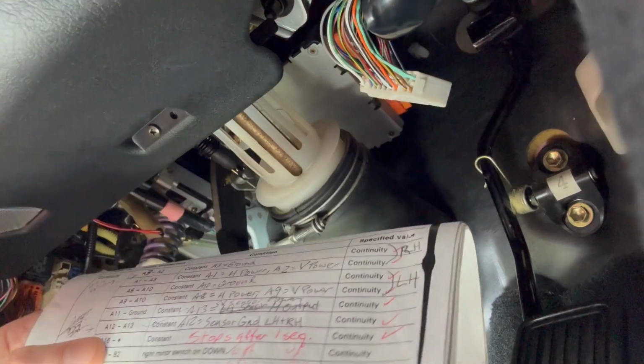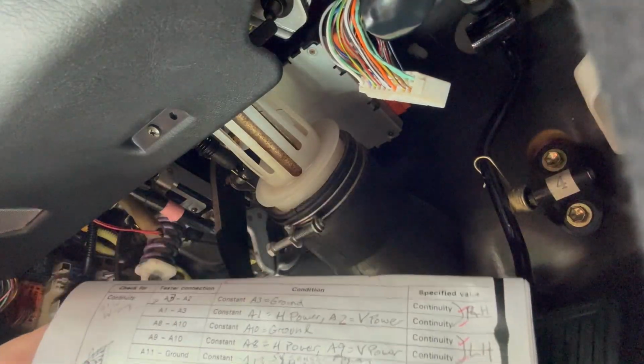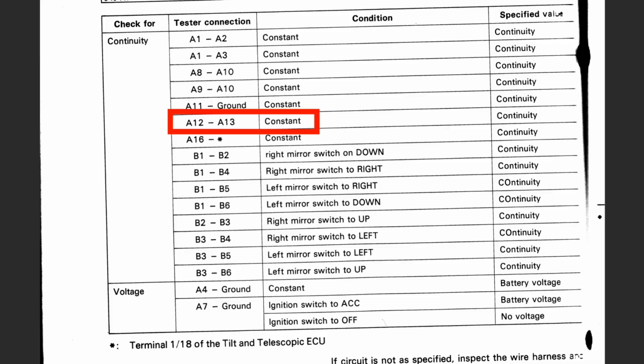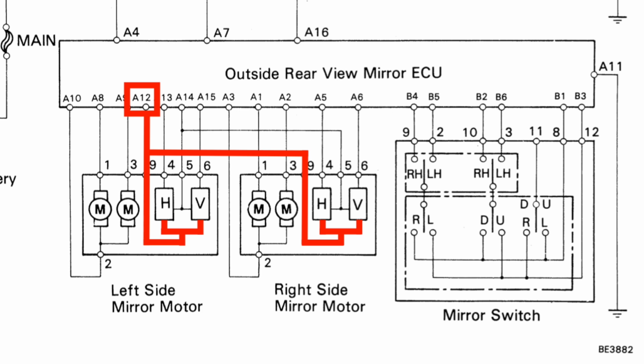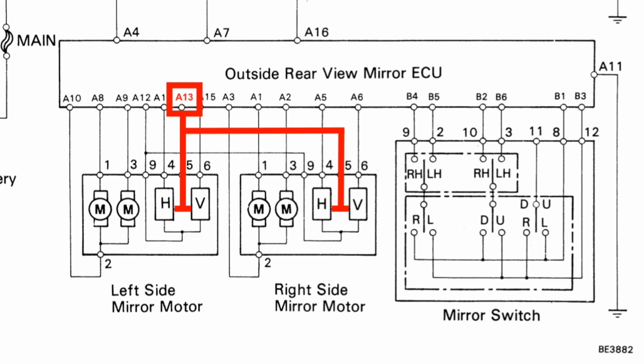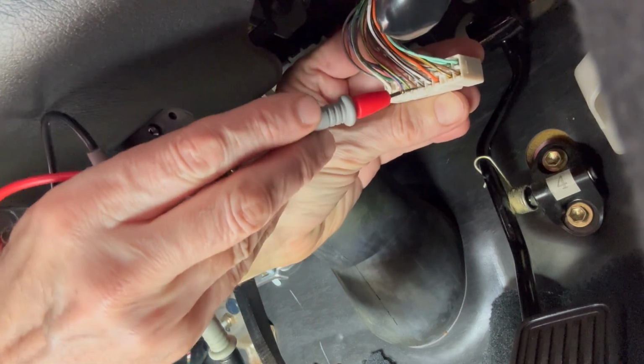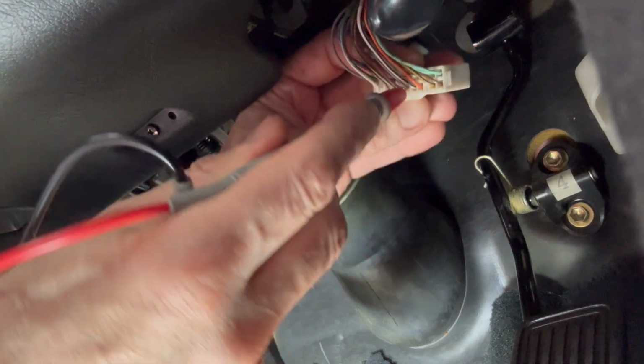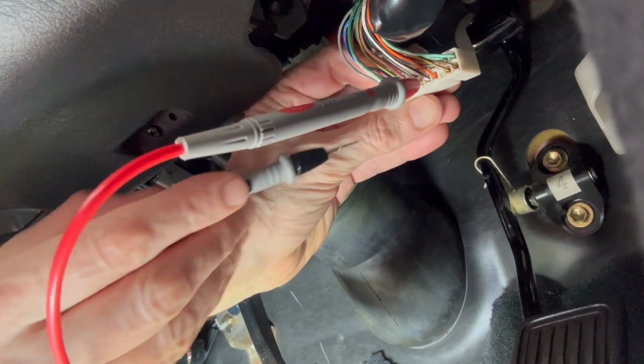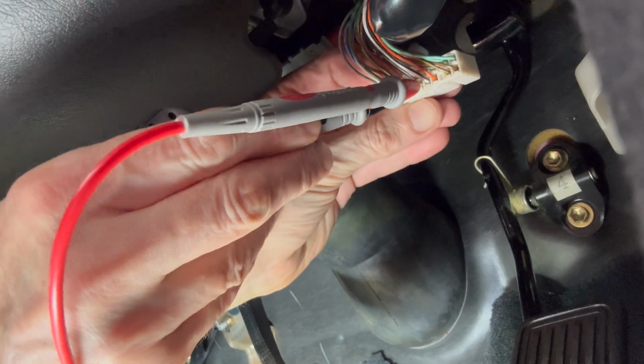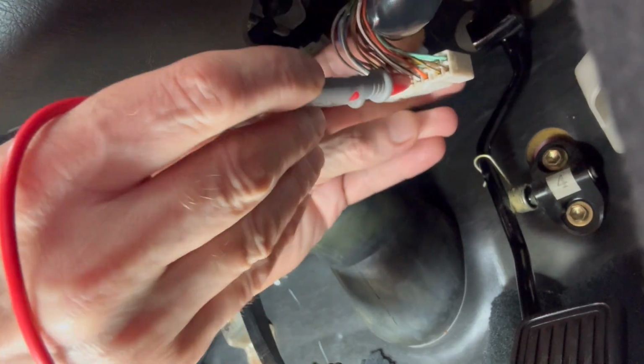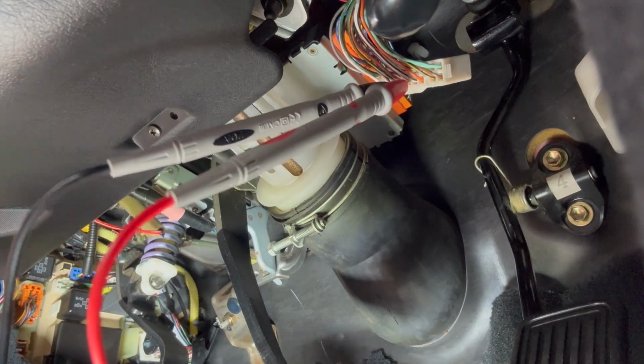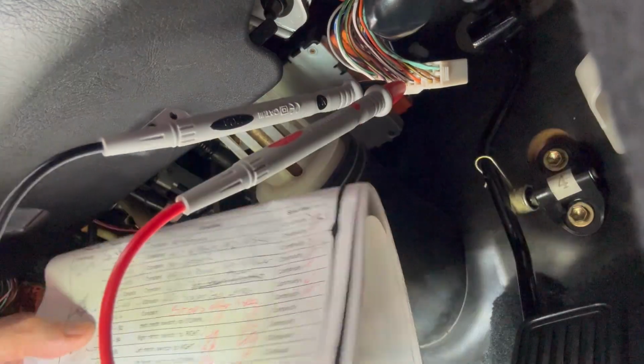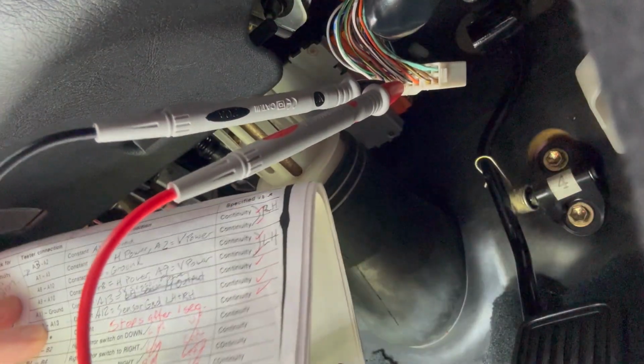I'll touch this grounded bolt. That's good. Now this test, A12 to A13, is about the sensors. A12 is sensor ground and A13 is sensor power. A12 is right there, next to it is 13. I'm not surprised we're not getting continuity on those, so testing A12 to A13 is questionable.